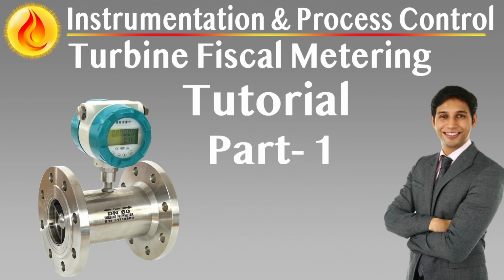Pressure and temperature sensor configuration. The pressure transmitter must offer digital signal output with analog redundancy, 4 to 20 milliamps, and support local diagnostics for drift, calibration status, and zero check functionality. The temperature transmitter must use a PT100 RTD element interrogated via a 4-wire circuit to minimize error due to lead resistance and to enable precision readings across narrow thermal spans.